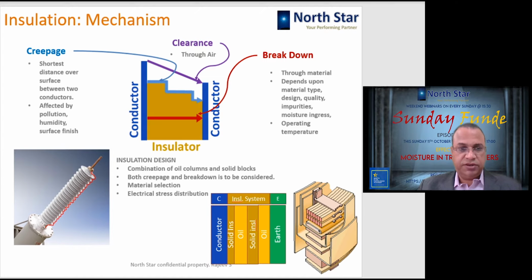Here you can see the image where I have shown a bushing, and with the red line we have drawn the creepage distance. So you can see, if this kind of shape had not been there, then the creepage distance would have been very little. This kind of shape is called petticoats. If these petticoats are provided, the creepage distance is made very large. So the surface distance, or the distance required for voltage to travel from the live point to the earth point, will be very big compared to normal circumstances. So this is why the bushings are designed in this manner.